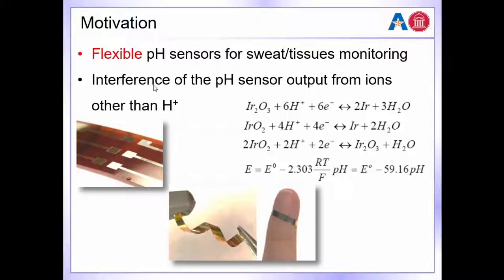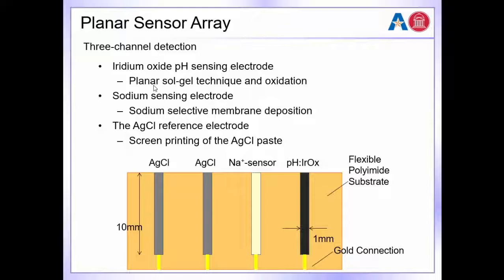For all these demonstrations, we did repeatability and reliability tests because it has to be very reliable, and we found there's an issue. The pH sensor is very often interfered with by ions other than hydrogen. For pH sensing, we are measuring the hydrogen concentration, but the redox of iridium oxide, which interacts with the hydrogen, is obviously affected by all these positive ions. Therefore, if your liquid, say sweat or blood, has other positive ions, you cannot avoid that the sensitivity of the sensor will be changed. And this is a big issue because our sweat has a lot of sodium. So we propose this method: can we integrate multiple sensors on the same substrate and use a sodium sensor to calibrate the pH value?